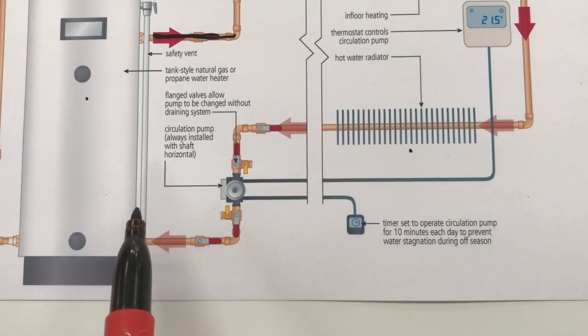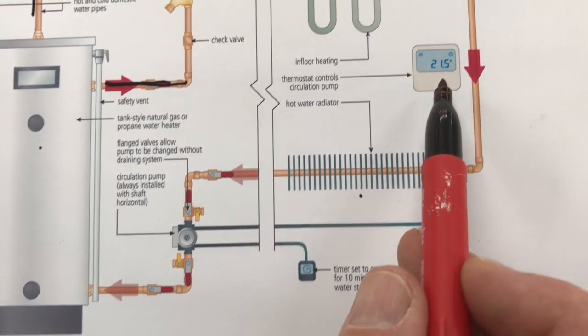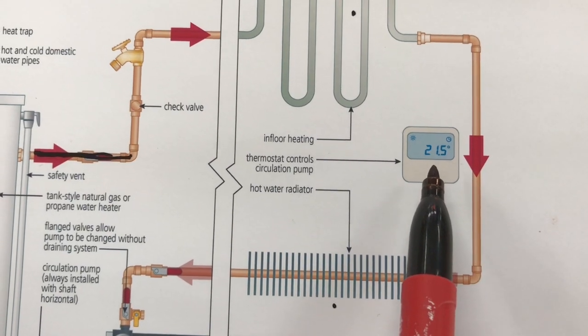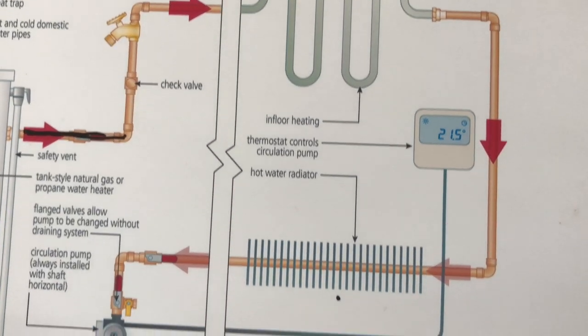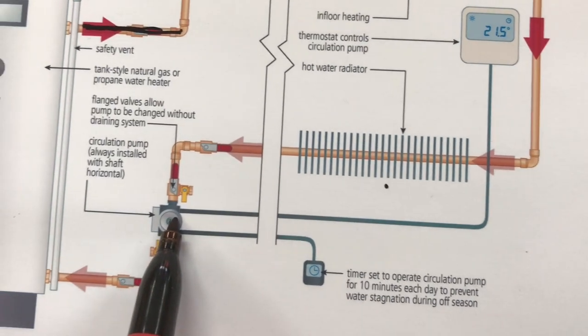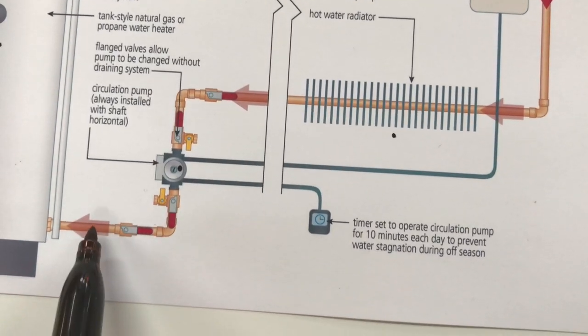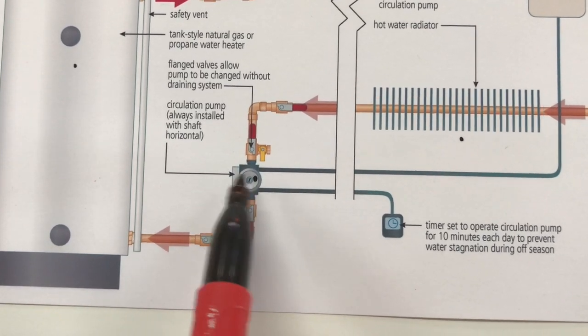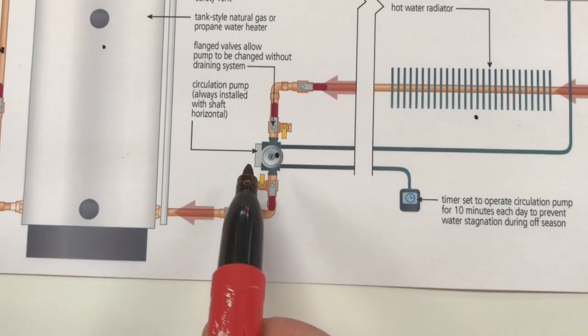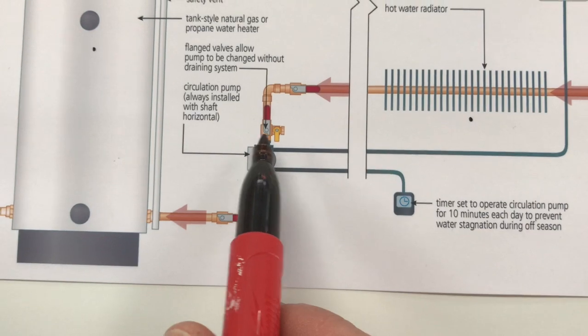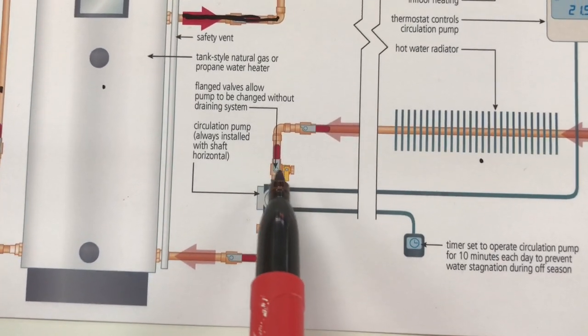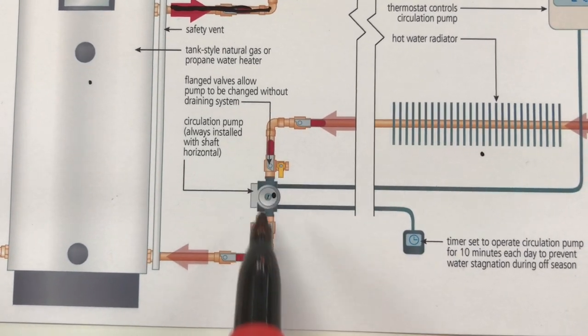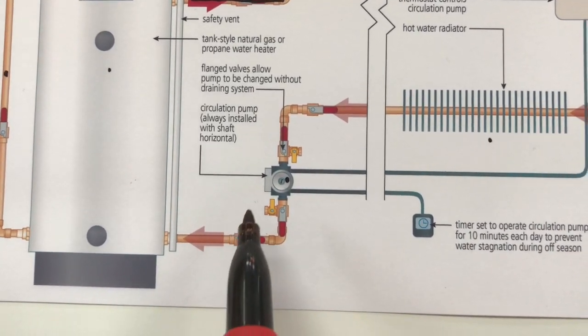Now all of this happens when the thermostat calls for heat. The thermostat detects that the room is too cold and it triggers this circulator pump here which starts the flow of water. You'll notice that the circulator pump is installed in a fairly low part of the system. This saves a lot of trouble because it means you're far less likely to have that pump prevented from working by an airlock.